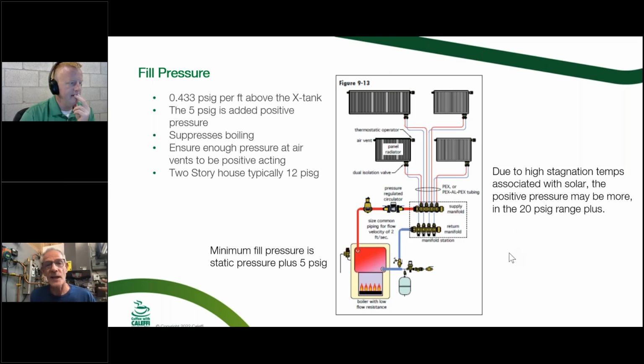And you can guesstimate that. If you round that number up to 0.5, and you take the height of the building, it's just half of that. So if you've got a 40-foot tall building, 20 psi gives you a little bit of wiggle room and makes the math so you can do it in your head. So now you've got to charge your tank. Before you put your tank onto the system, you want to put your air gauge on the bottom and make sure that it is set at that number that you came up with, let's call it 12 plus 5, 17 maybe on this system.